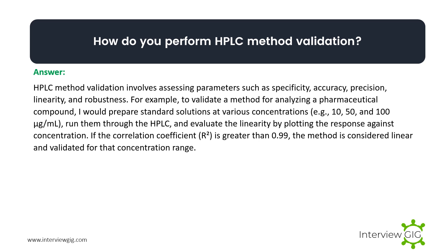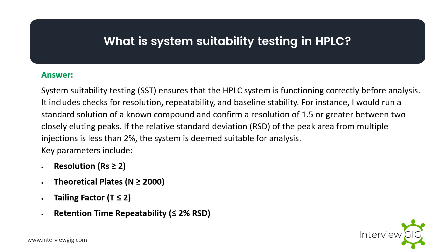How do you perform HPLC method validation? HPLC method validation involves assessing parameters such as specificity, accuracy, precision, linearity, and robustness. For example, to validate a method for analyzing a pharmaceutical compound, I prepare standard solutions at various concentrations, run them on the HPLC, and evaluate linearity by plotting the response against concentration. If the correlation coefficient is greater than 0.99, the method is considered linear and validated for that concentration range.